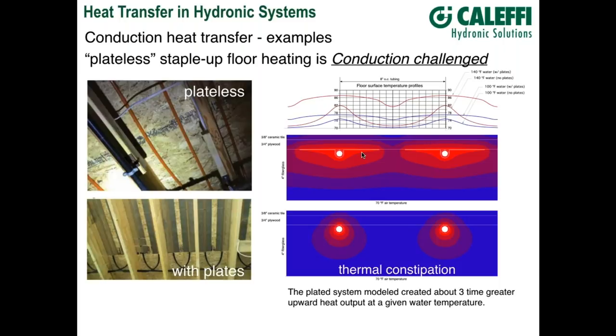Without plates, you create hot spots directly above the tube and the temperature drops off quickly on both sides. We've come up with a term for this: thermal constipation. The plateless system is a thermally constipated system. We could put 150 or 160 degree water in there, but the combination of different materials, their thermal conductivities, and the geometry — think about a round tube against a flat surface giving very limited contact — severely limits heat transfer.